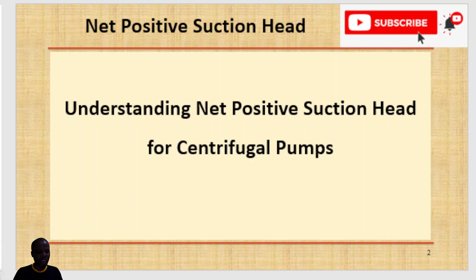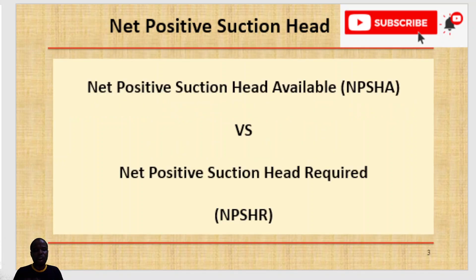When this pressure is not sufficient to prevent vaporization, the phenomenon known as cavitation occurs, causing damage to the impeller, reduction in the pump's developed head and capacity, and ultimately results in noise and vibration. So when we talk about NPSH, which is the net positive suction head, there are two categories.